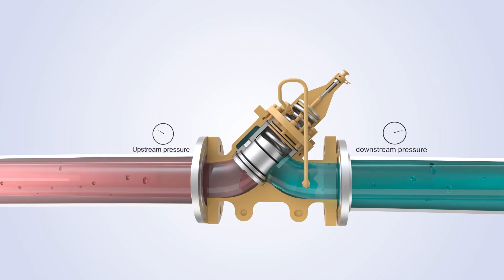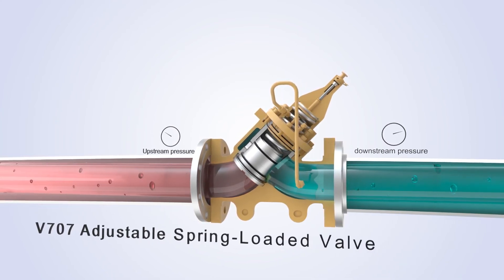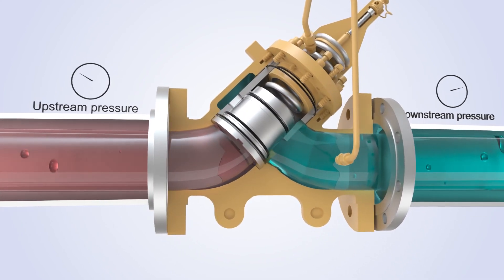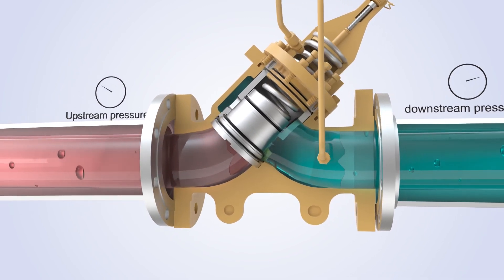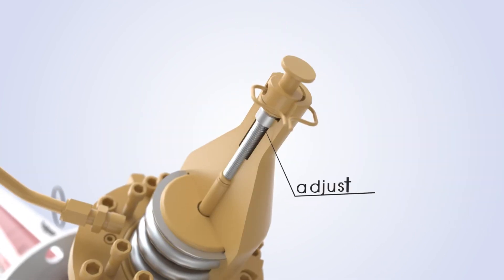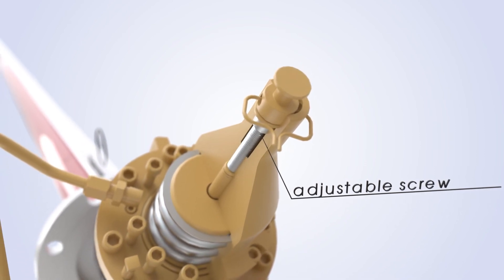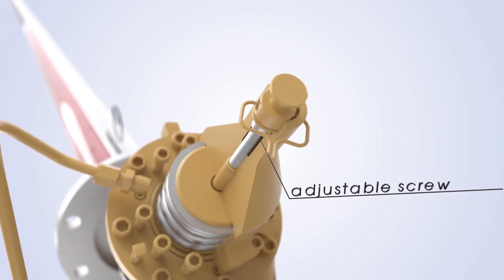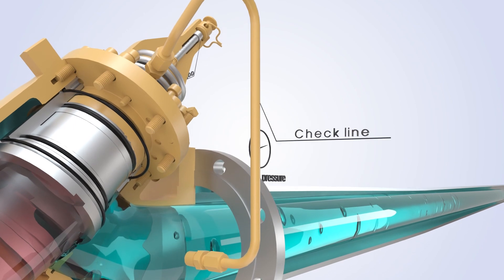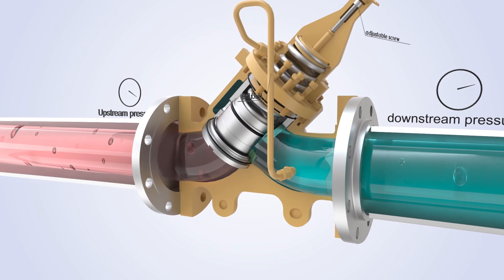As a third example of optimized controls for the 700 series, the V707 adjustable spring-loaded valve is both simple and effective. The valve maintains upstream pressure or back pressure in the line by having the piston remain seated while upstream pressure is lower than the spring force and downstream pressure combined. The force of the spring is modulated by a screw located inside the spring cover, which provides easy adjustment of the set point pressure. The V707 also includes a check line to equalize pressures on the valve downstream and the backside of the piston, closing the valve in the event of a sudden increase of downstream pressure.